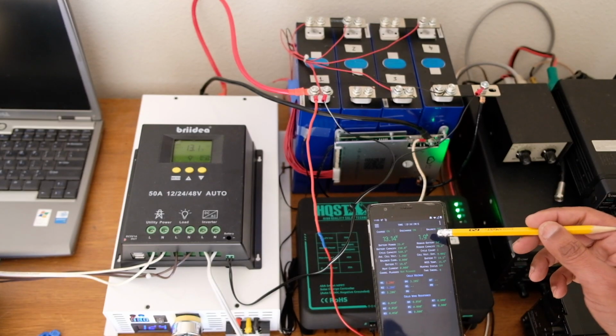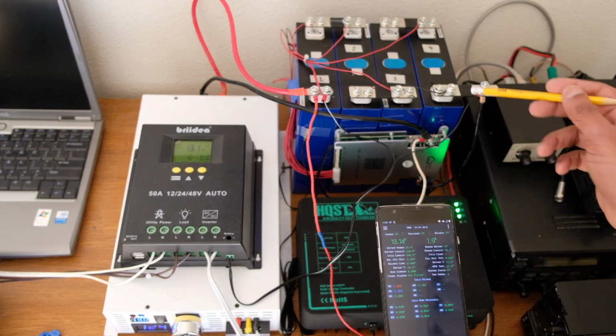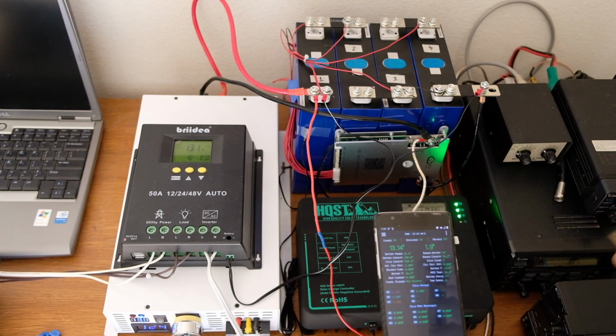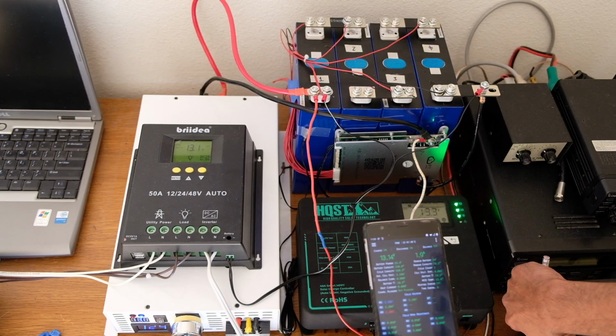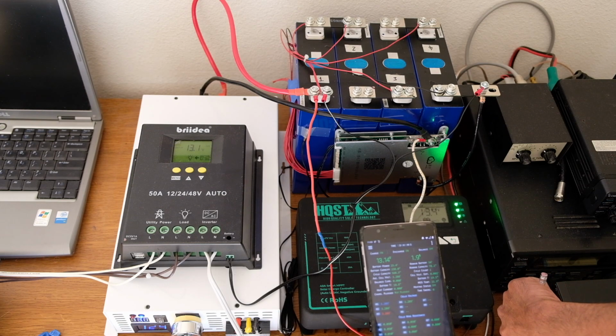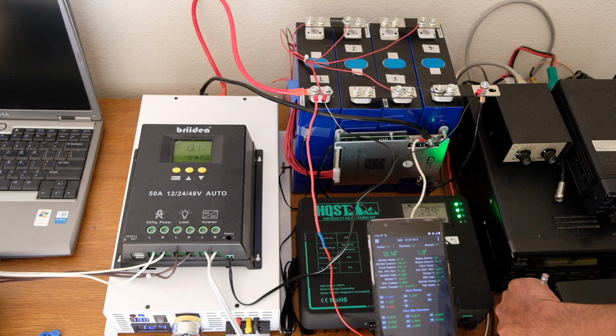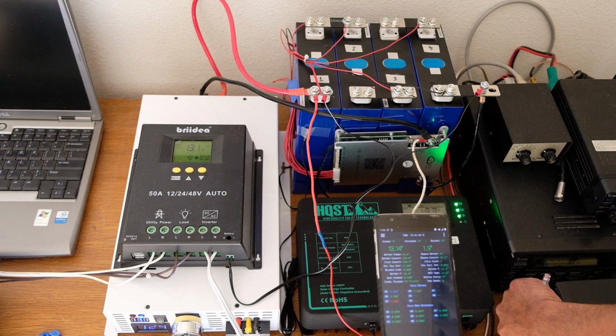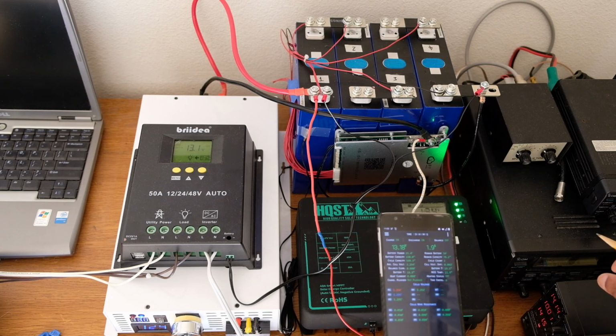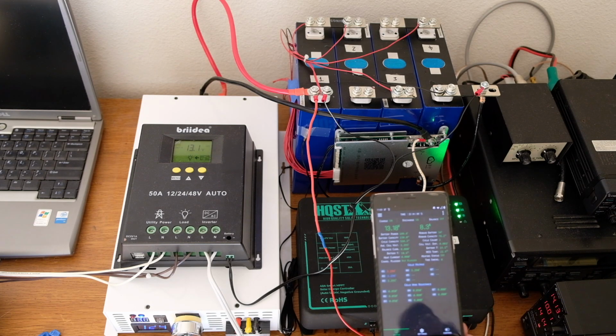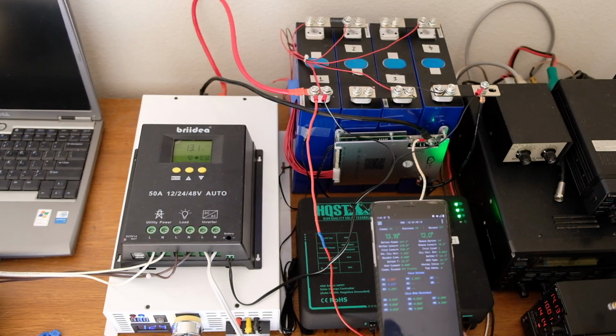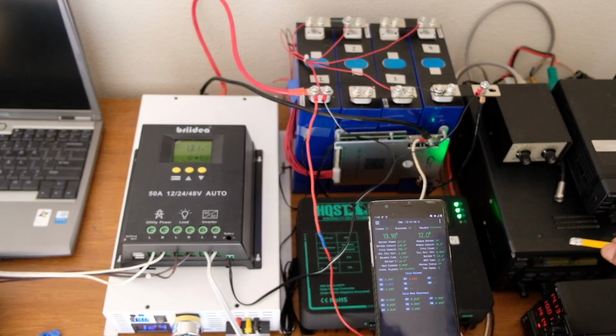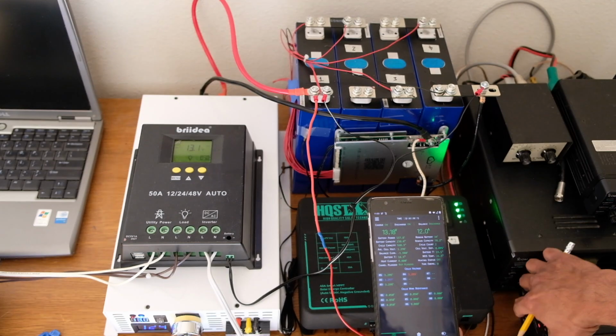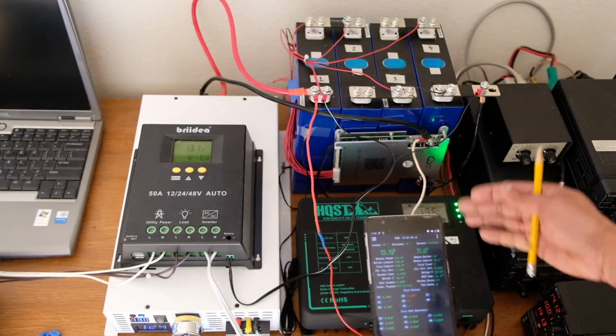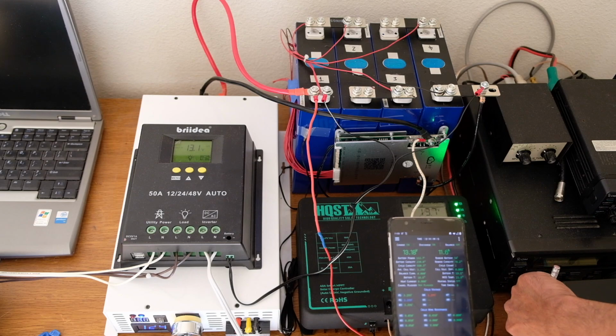Right now it's getting 2 amps of charge going into the battery while it's also driving the load. If I turn on my DC power supply to compensate for some of this, to basically charge the system as well, I'm turning it on now, and you can see it's gone up to 8.3 amps. So this is providing around 10 amps of current at 14.4 volts. And when this battery is fully charged, the BMS will basically shut off the charging part of it.